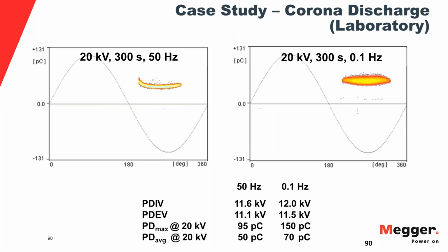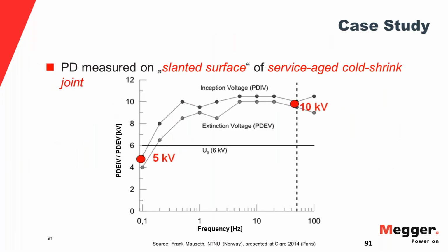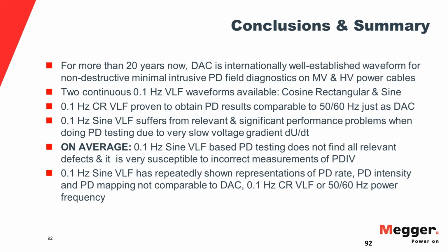And then that is a fairly recent publication that is also interesting, because it tells you, well, in these refractive field control elements in the joints, it's really important to have something that is comparable to power frequency to be able to get a correct assessment under operating voltage condition. And I believe this is the conclusion of everything.